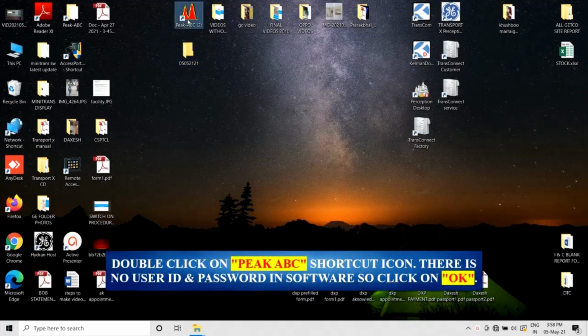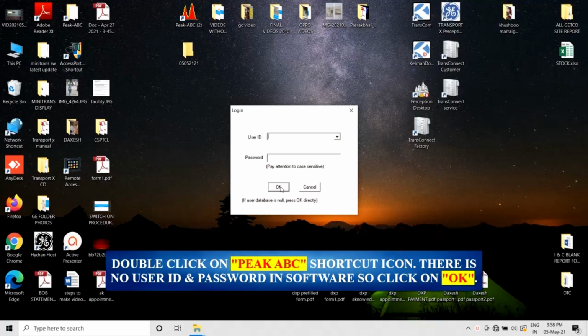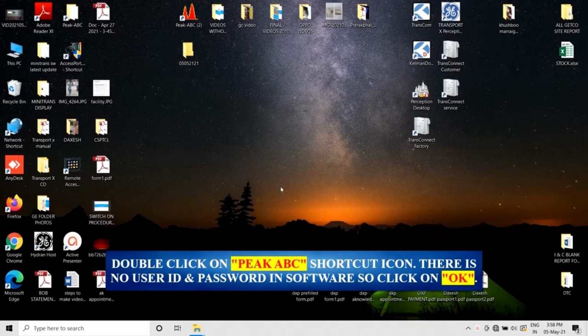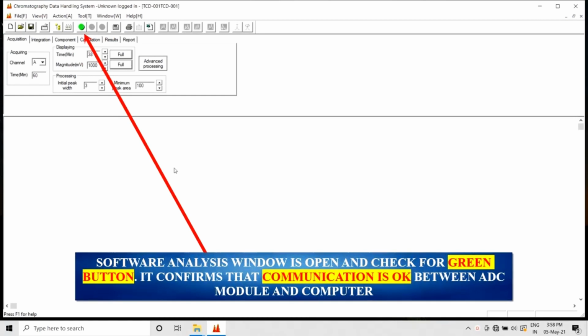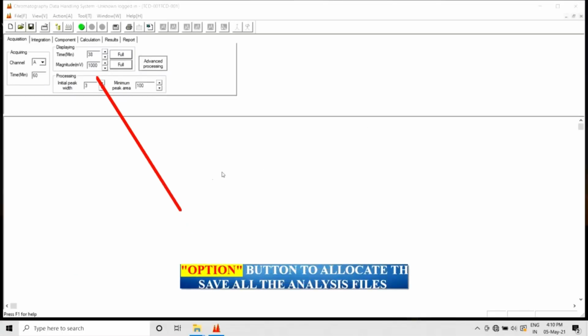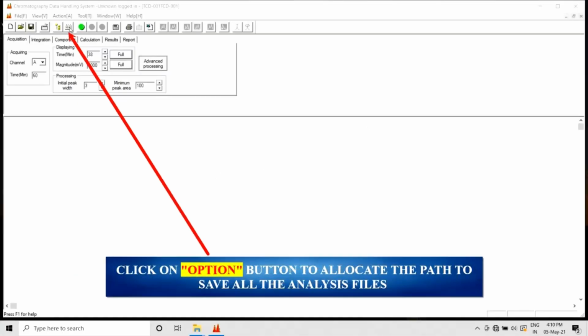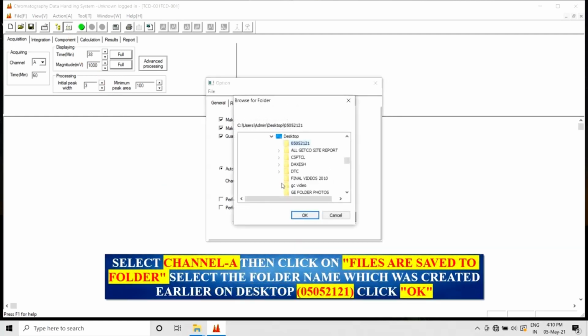Double-click on the Peak ABC shortcut icon. There is no user ID and password in the software, so click on OK. The software analysis window is open; check for the green button. It confirms that communication is OK between the ADC module and the computer. Click on the Option button to allocate the path to save all the analysis files in that folder. Select Channel A, then click on Files are saved to folder. Select the folder name which was created earlier on the desktop, 05052121, then click on OK.